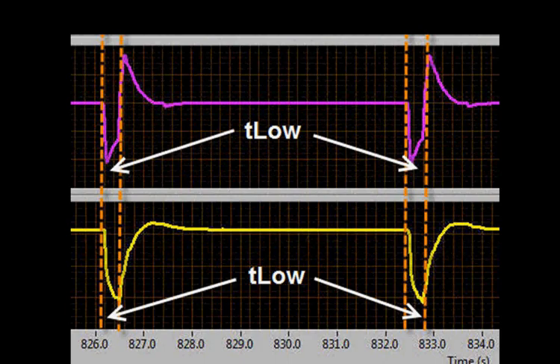The T-Low setting sets the time interval for the low pressure or low CPAP phase. Allowing for intermittent release in airway pressure, this provides CO2 removal and partially unloads the work of breathing related to pure CPAP breathing. Note: T-Low should not be considered expiratory time, as the patient may exhale throughout the entire inspiratory phase.